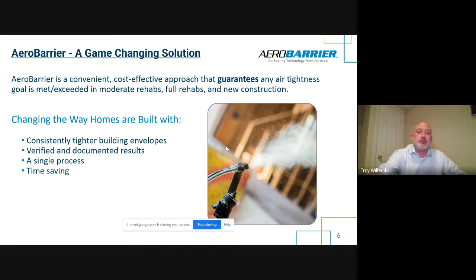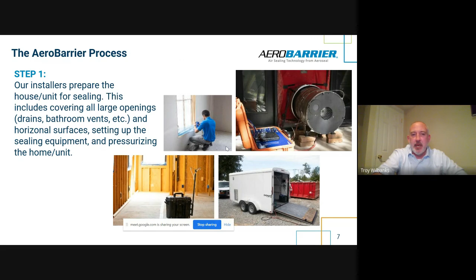So, hop into the process itself. It's very simple. It's 3 steps. The first thing we do is prep the unit. So we come in and we tape off any of the designed openings. That's windows, doors, fireplaces, things of that nature. Then we take a modified blower door and put positive pressure into the space and pressurize it to about 75 Pascal.